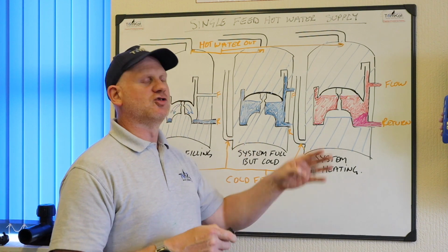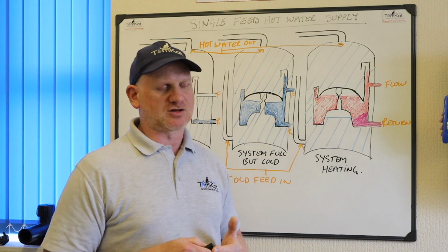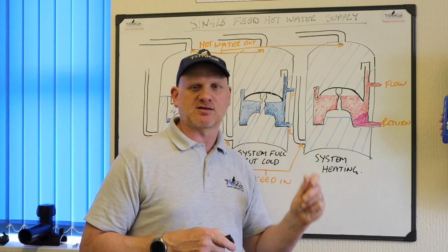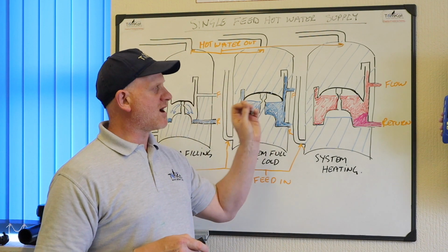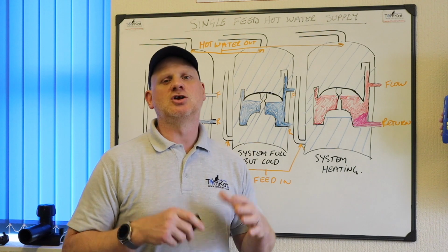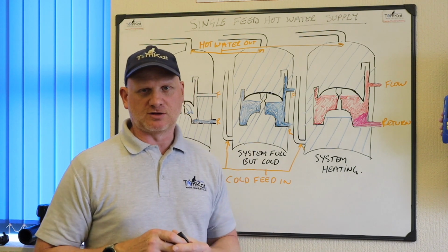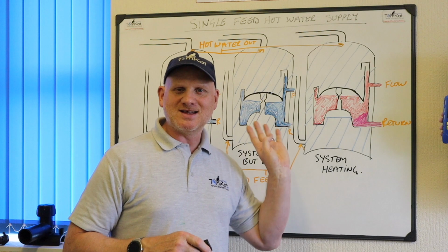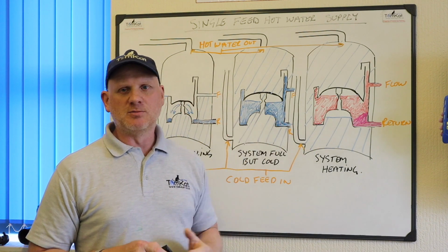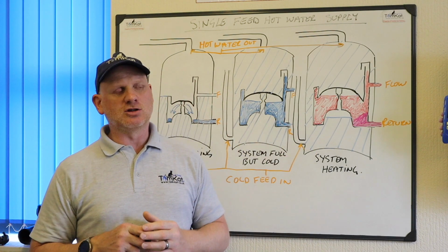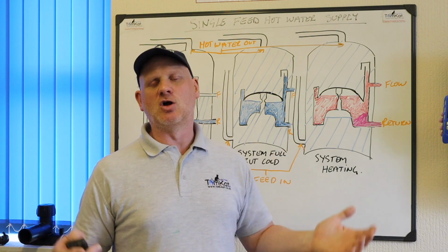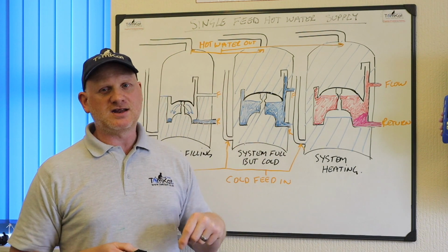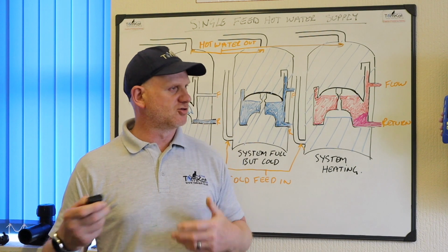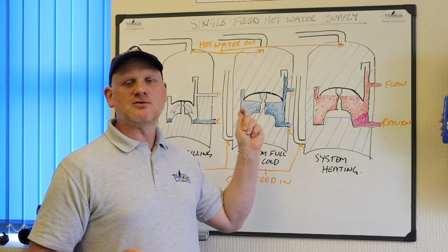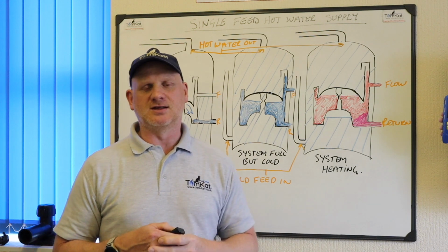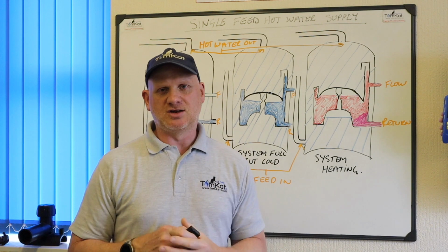So it would force the water around the gravity circuits. You cannot do that with a PRIMATIC cylinder. If you try and boil a PRIMATIC cylinder, you will break the bubble. It will be useless. Just actually draining this system down can ruin the bubble. You're always running that gauntlet for a 30, 40-year-old cylinder that once you've drained it down to do any repairs or any alterations, you're running the risk of damaging the bubble inside the cylinder. Once it's damaged, it's a new cylinder.